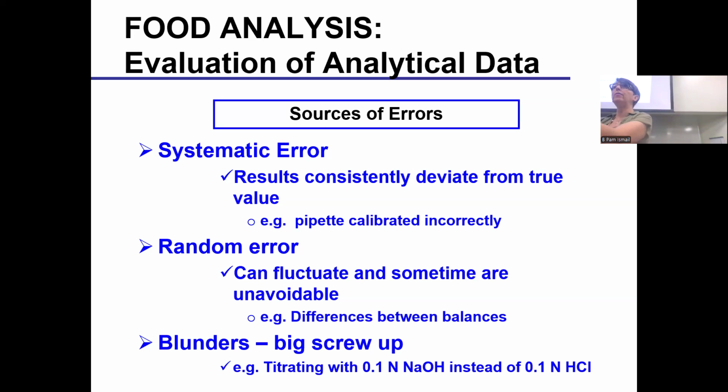You're working with a mechanical pipette we gave you. We did not calibrate it for you, or we didn't do a good job calibrating it. So you are dispensing what you think is 1 ml, but it's always dispensing 0.9 ml instead of that 1 ml. So it is systemically giving you the wrong volume. Your precision will be very high if you know how to pipette, really high, but it's inaccurate. Okay, so that's systematic error.